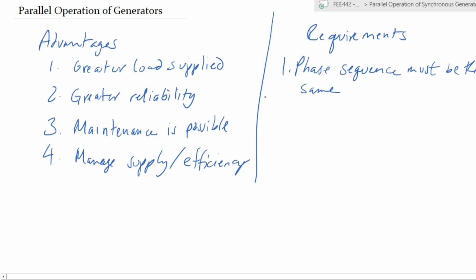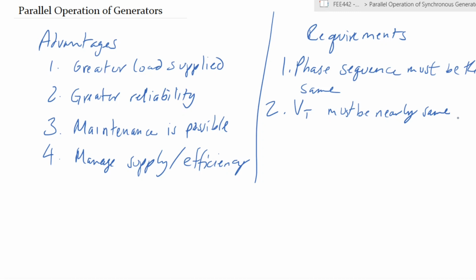Secondly, terminal voltage must be nearly the same. So if your generators are running at 11 kV, it should be approximately that voltage. If the system voltage is 11 kV, your generator should be operating at close to that. This will allow it to match up with the system when it actually joins.